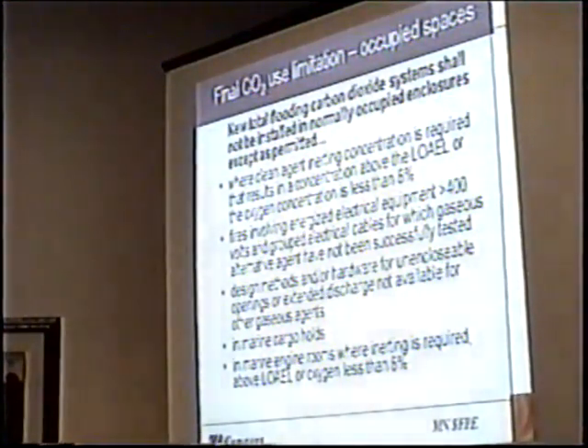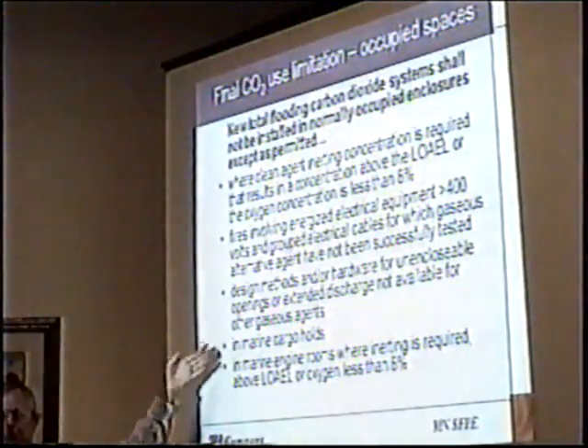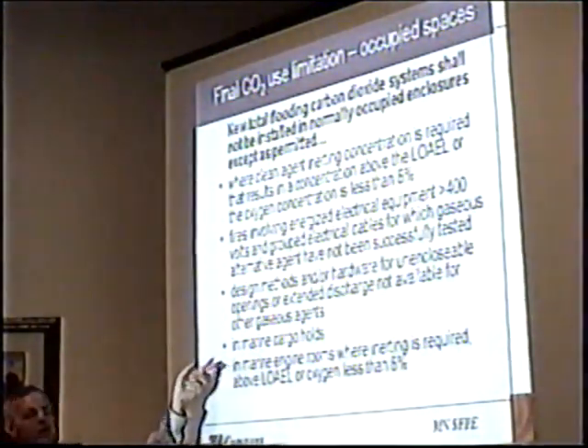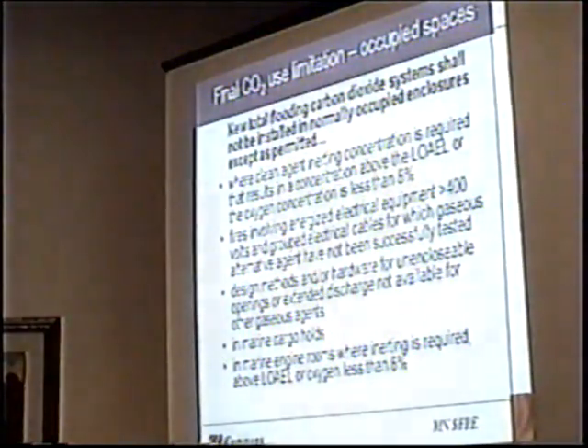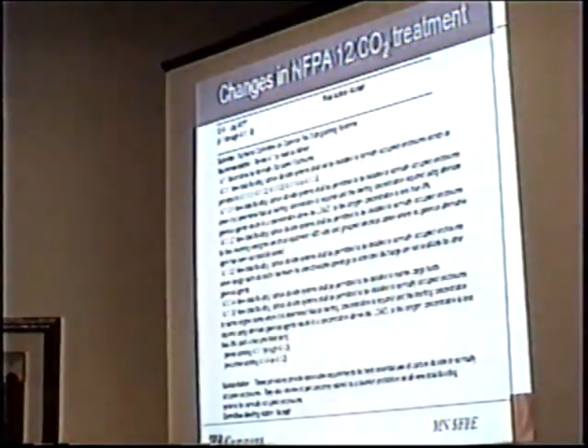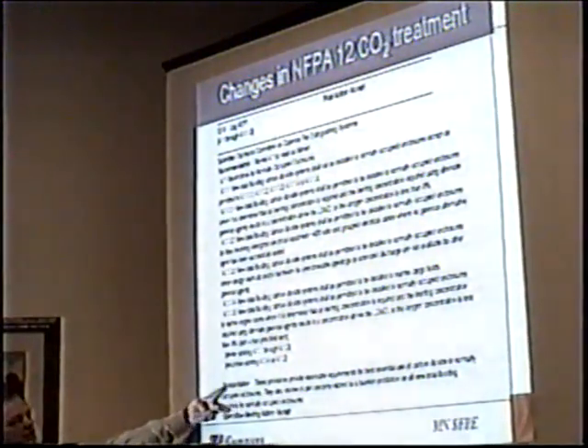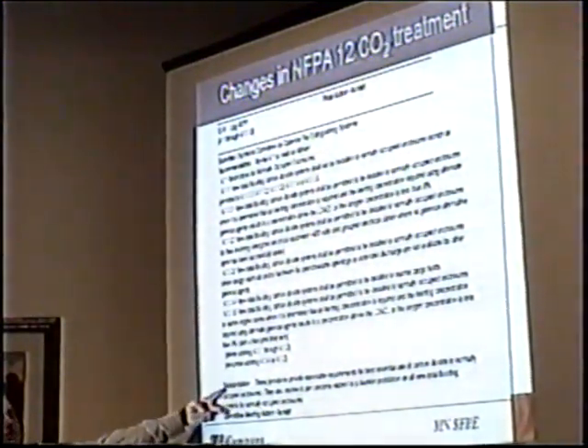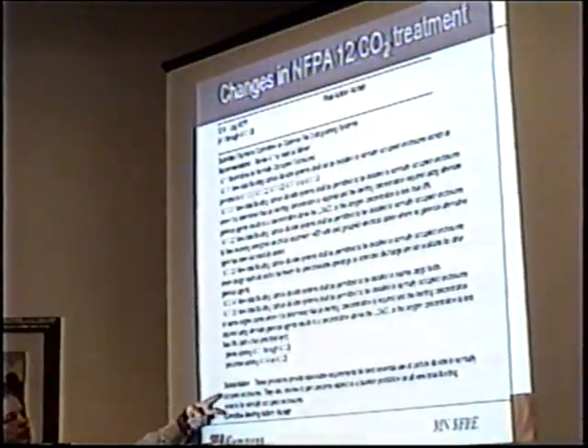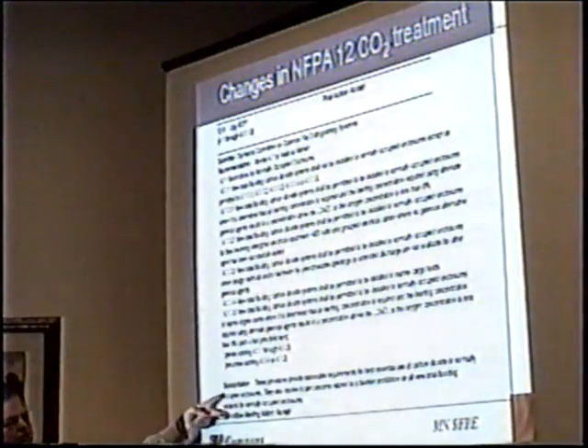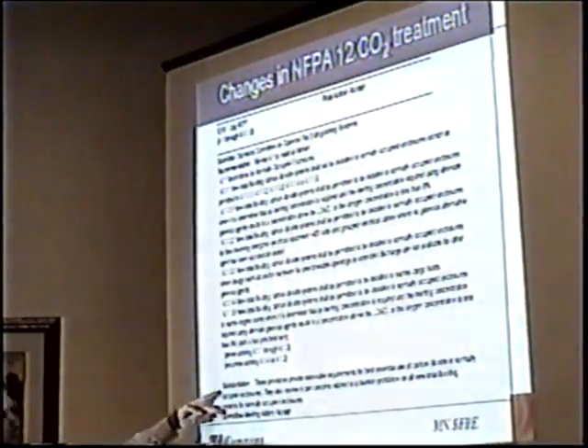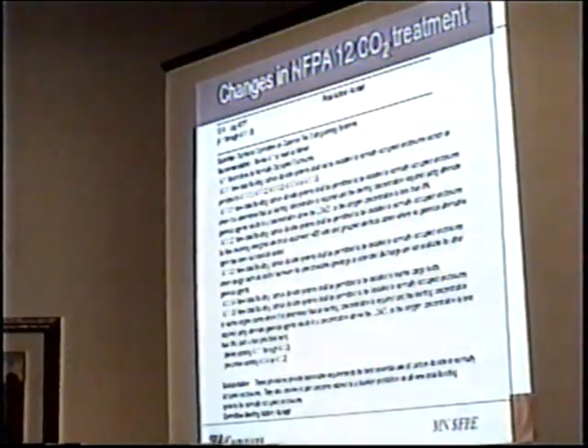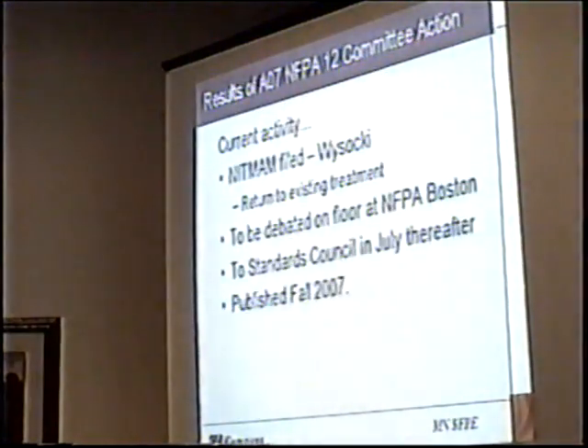Marine cargo holds is a takeout on this because there isn't a real good solution for that, and CO2 is shown to work well in that. No other clean agents have been used for that application. And then marine engine rooms, again, where a higher concentration is required. This is what it looks like in the final ROC, but down here, the substantiations: these provisions provide reasonable requirements for the essential use of carbon dioxide in normally occupied enclosures. These also resolve in part concerns related to a blanket prohibition on all new total flooding systems for normally occupied spaces. In other words, what EPA wanted to do was get to a point where they didn't outright ban it, but limited it to the point where its use is minimal in that application.